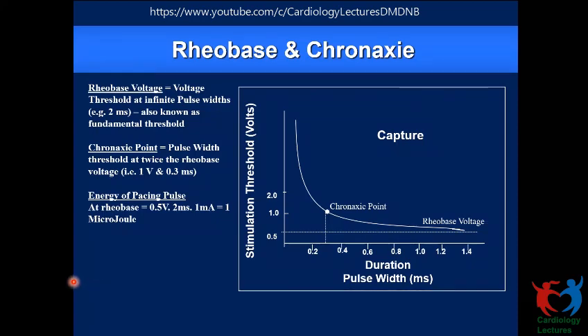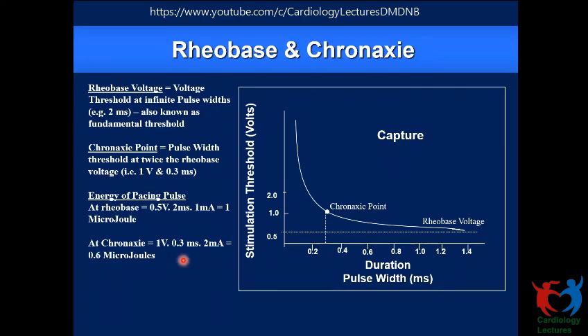Then we can also calculate the energy outgo at the chronaxis point, and our chronaxis point is 1 volt, and the pulse width threshold worked out to be 0.3 millisecond. So when we apply Ohm's law, in this case, the current outgo is 2 milliamperes. Then the energy outgo in this case is 0.6 microjoules. This is also a threshold point, but you can see that the energy outgo at the chronaxis point is less than what it was at the rheobase point. So the chronaxis point is the sweet spot where the energy outgo is the least.